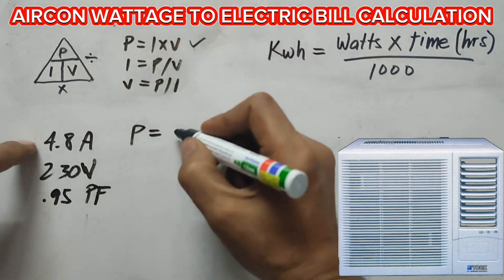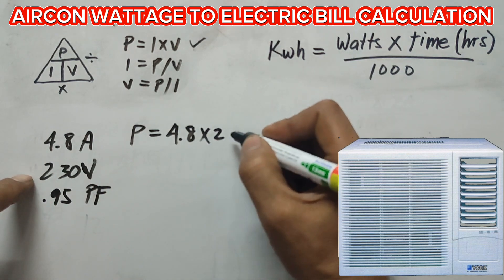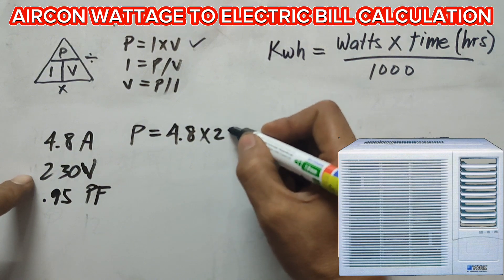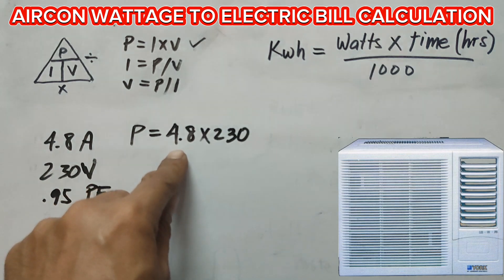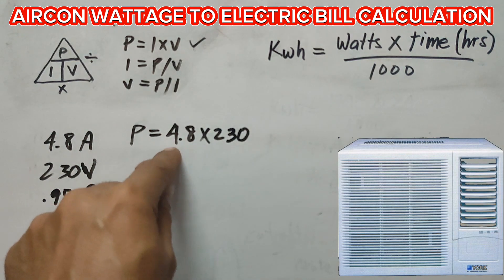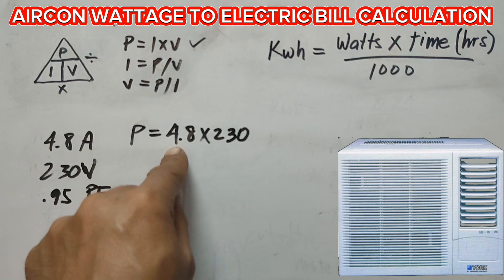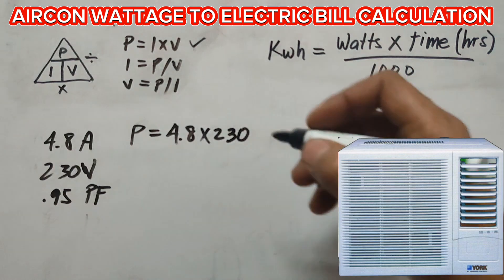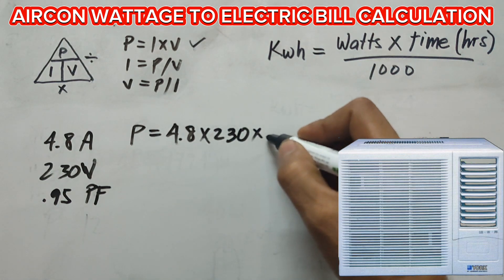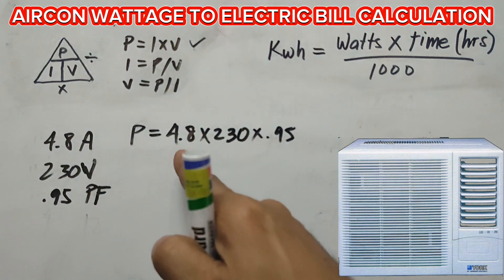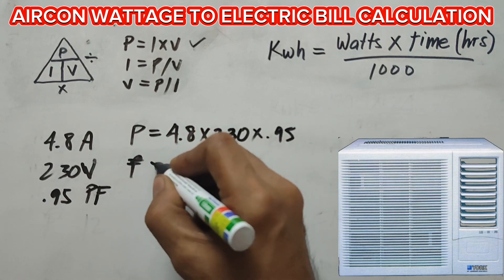We're going to apply the formula: P is equal to I times voltage times power factor. So P is equal to 4.8 times 230 volts. If you have 220V in your place, use 220. For example, in the Philippines it typically ranges from 3.5 to 3.8 ampere for one horsepower — use whatever ampere reading you got on your air conditioning unit. Then multiply by the power factor 0.95.